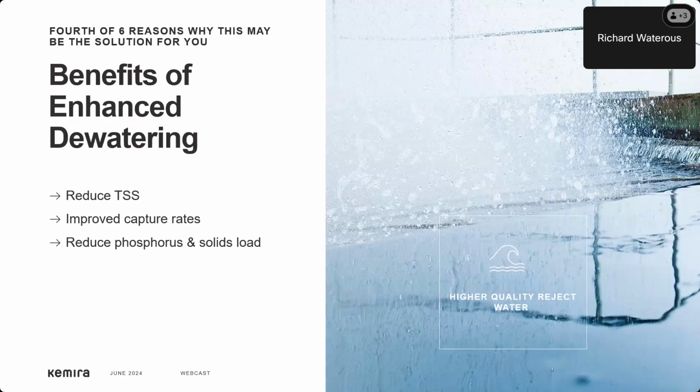Ferric addition for enhanced dewatering yields improved solids and phosphorus capture rates, resulting in higher quality centrate filtrate quality returned to the plant's treatment process. Reduced TSS and phosphorus levels returned to the treatment process contribute to improved treatment plant performance and reduced costs relating to the chemical usage if CEPT is utilized, as well as improved aeration operation.